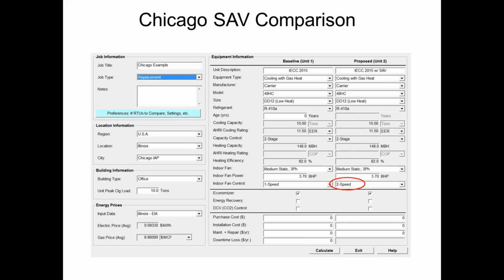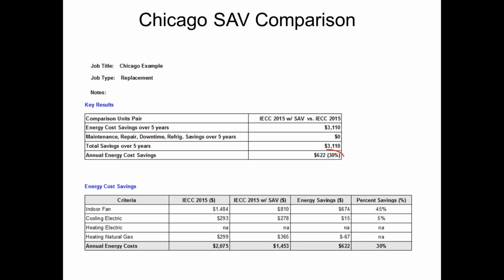So let's see how much energy that saves. If I take my code compliant unit, which is an IECC 2015 IEER type unit, plus the Economizer that's usually required, I take that exact same unit, same model, same everything, and all I change is by putting a 2-speed fan on it instead of a 1-speed fan, I'm going to save about 30% energy. So that's a pretty hefty chunk of energy savings from going from a 1-speed fan to a 2-speed fan.